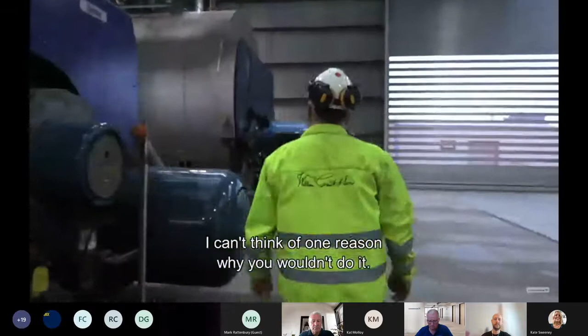So, yes, his modulating valve issues have gone away because we've taken the modulating valves away. He's got better steam quality, smaller pumps. The other interesting thing was the gas usage - because the boilers are operating more efficiently, they reduced their gas usage by between 3 and 5%. And when you bear in mind they're spending £1.4 million a year on gas, that was also quite significant.